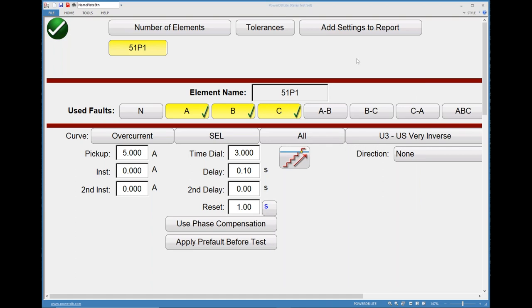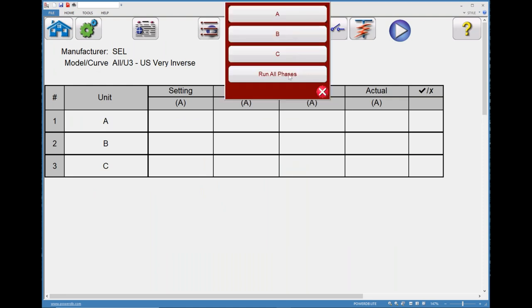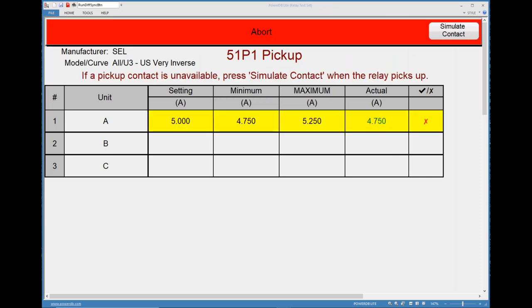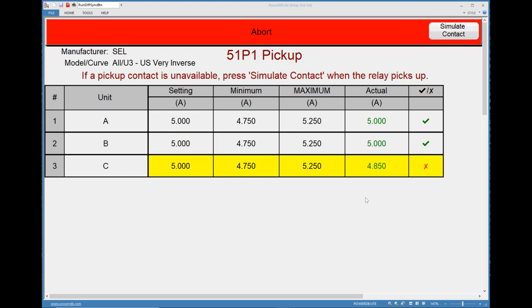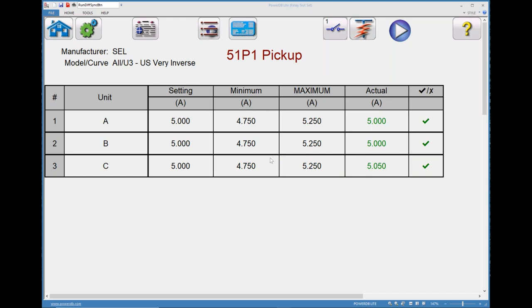Now I go back to the test, hit the check mark — 51P1 pickup, ready to go. I want to run all the phases at once. The test set is now running. You're going to see the min and max values — plus and minus 5% from the tolerance screen — and it's actually ramping this value until the relay operates. Once the relay operates, it'll come back and report the value to us, and we can use those in our results. A little bit over — that's okay. We just completed the first test. It takes me longer to talk through it than it does to configure the test.